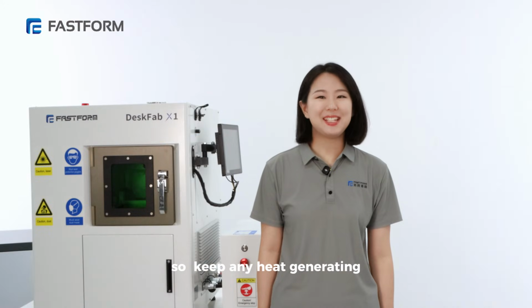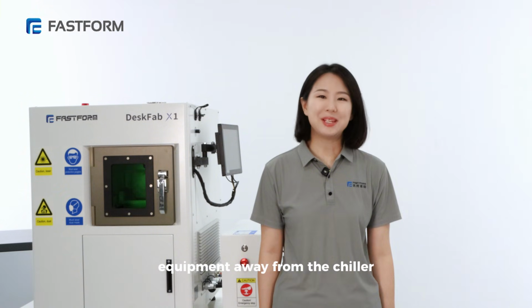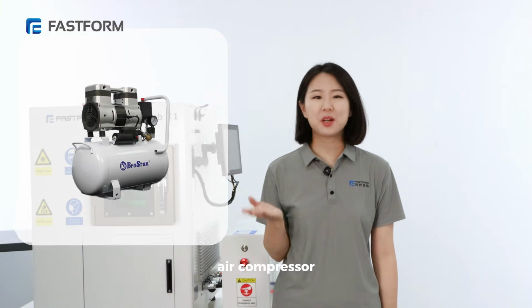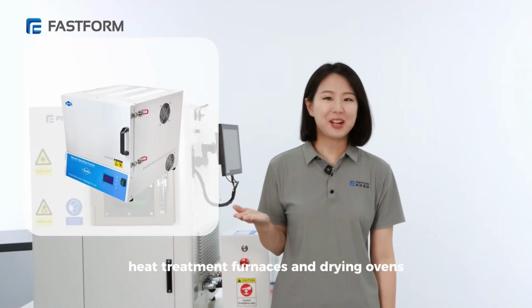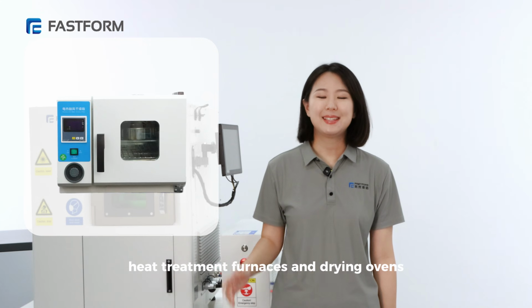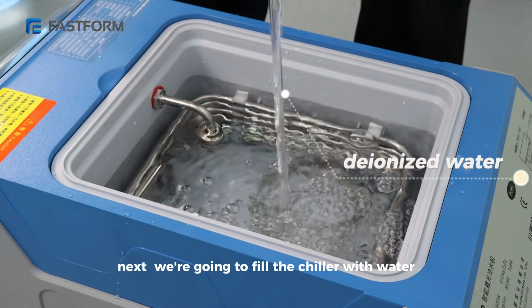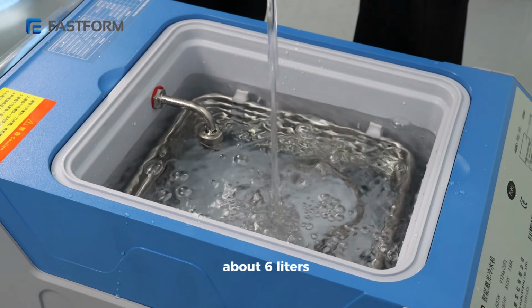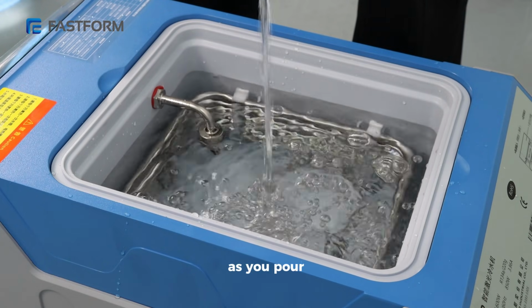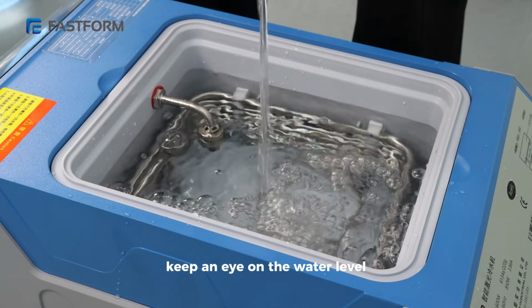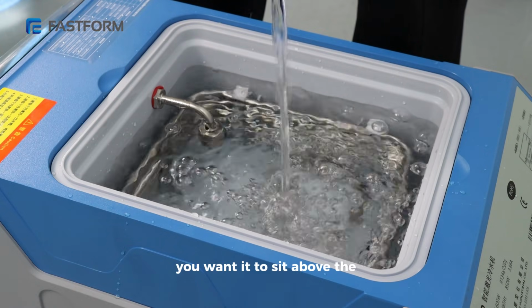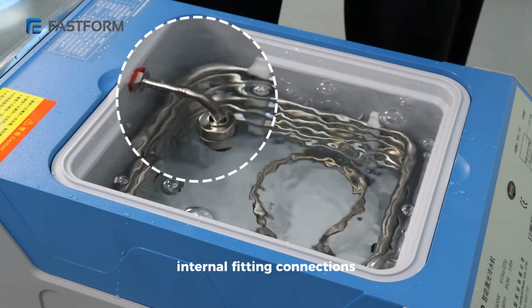So keep any heat-generating equipment away from the chiller. For example, air compressor, heat treatment furnace, and drying ovens. Next, we're going to fill the chiller with water, about 6 liters. As you pour, keep an eye on the water level. You want it to sit above the internal fitting connections.